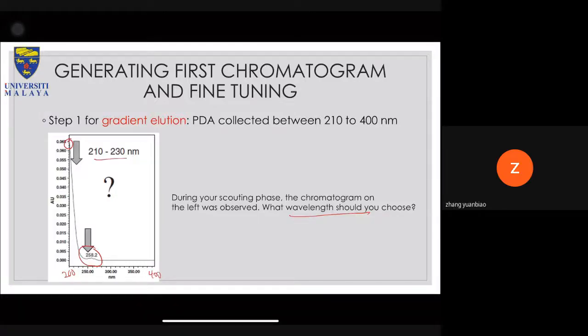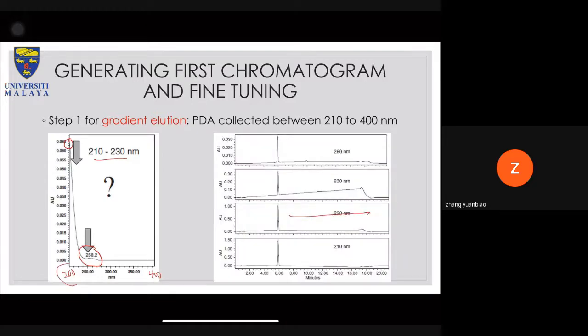So you want to choose a wavelength that is not too high and not too low. Why not too low? Because sometimes, especially if it's so close to the near UV, you might get a lot of high background reading. If you choose, for example, 190 nanometer, you will definitely see quite high background reading. So you want to choose something that is high, but not too low. Okay, like for example, something like that. 260 might not be your choice of interest.